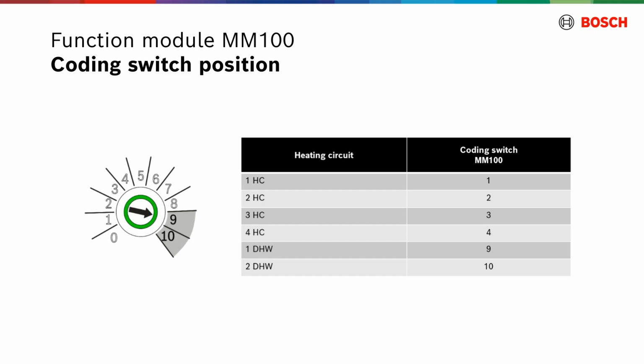If the coding switch is in a correct position, the status indicator lights up green continuously. In case of fault on the control unit, or if the maximum cable length of bus connection is exceeded, the status indicator starts flashing green. If the coding switch is not in a correct position or is in an intermediate position, the status indicator starts flashing red. When the status indicator lights up red continuously, it means internal fault, and the module should be replaced.